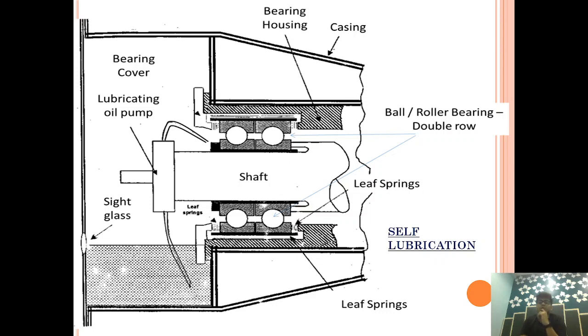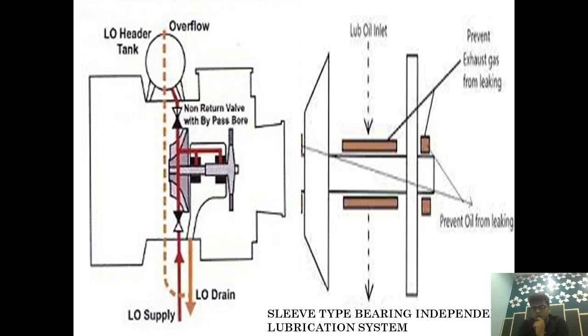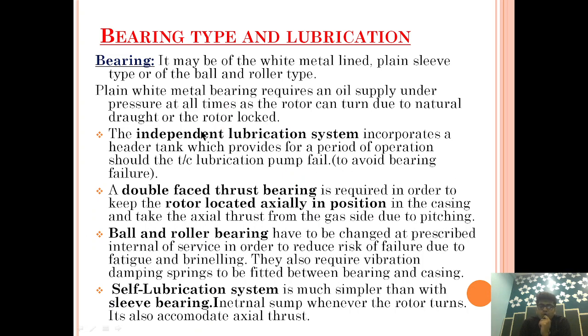If anybody asks what the lubrication systems are, there are two types: Self Lubrication and Independent Lubrication System. The Independent Lubrication System incorporates a Header Tank which provides oil for a period of operation should the Turbo Charger lubrication pump fail. Second, a double-face Thrust Bearing is required in order to keep the rotor located axially in position in the casing and take the axial thrust from the gas side due to pitching. Ball Bearings and roller bearings also need to be changed at prescribed intervals of service to reduce the risk of failure due to fatigue and brinelling. They also require a Vibration Damping Spring fitted between the bearing and casing — this is the Leaf Spring.